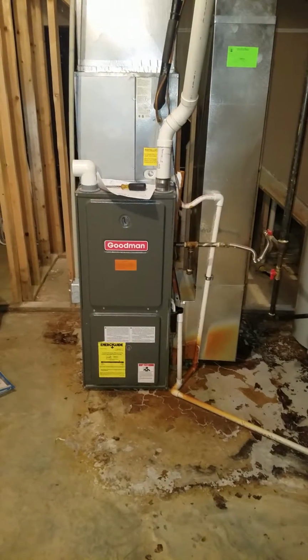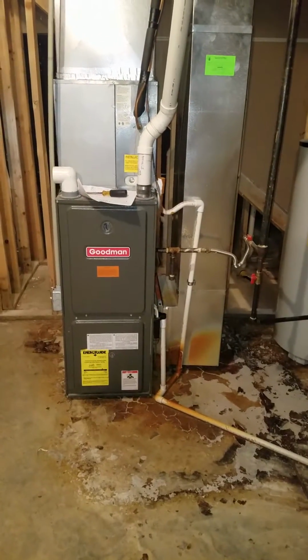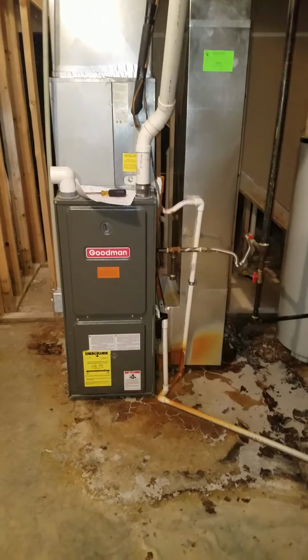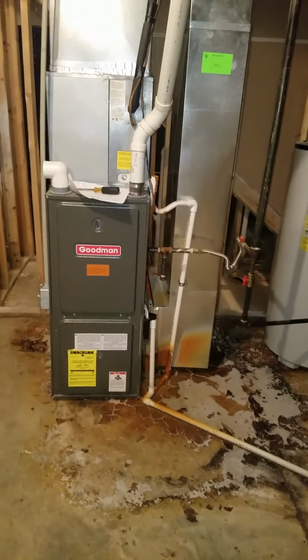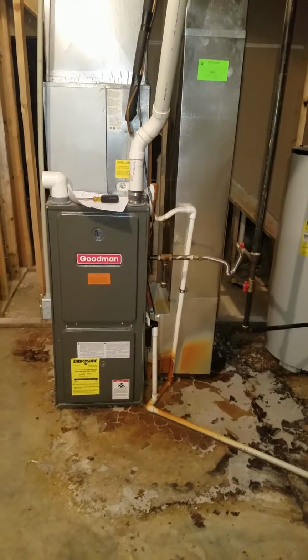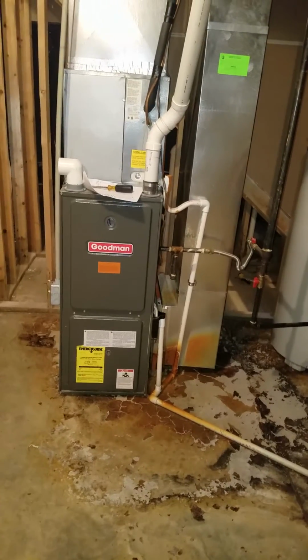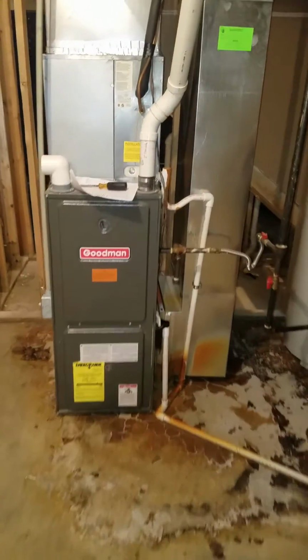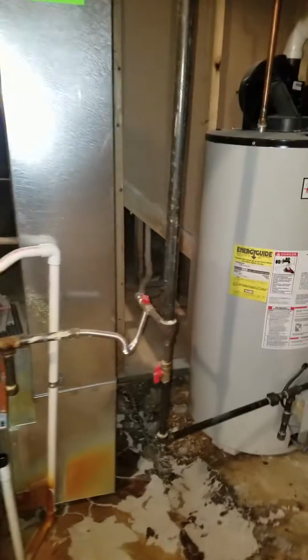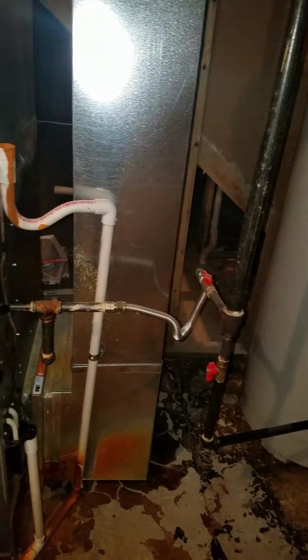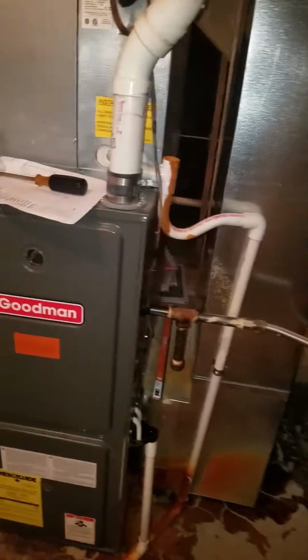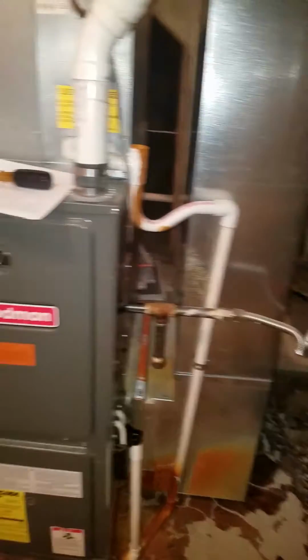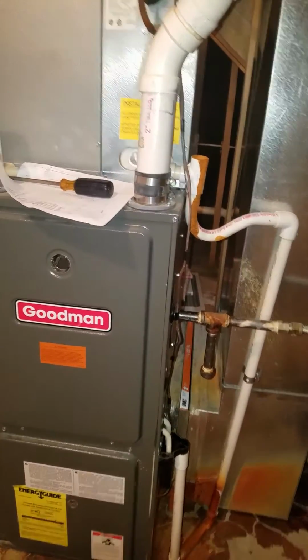I am at the Stibbins residence, and I'm in the basement area, and I'm looking at an upflow 80% Goodman furnace, 2004 model, 70,000 BTU. Here is your gas line coming in. You've got a 3/4 flex and the 3/4 black iron with the drip leg, and also going into the furnace.